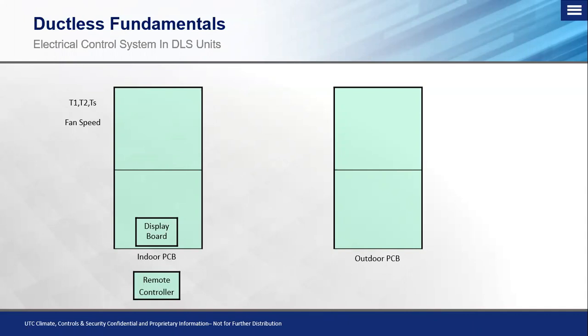The board inside of there has logic that registers when that fan speed is too low or too high. But more importantly, during normal operation, it needs to know how fast that fan speed is running and whether it needs to increase or decrease based on a user set point, or if the fan's in auto mode, based on a particular temperature on that indoor coil. Okay, from there, we have that information that's fed over into the indoor board, and in turn, we get control for the indoor fan motor for different speed settings. And if your unit is capable of having a swing feature with the louver, it will receive a command from the wireless remote controller, and then in turn, execute that command and either swing that motor or adjust that louver's position, again, if your unit has one.